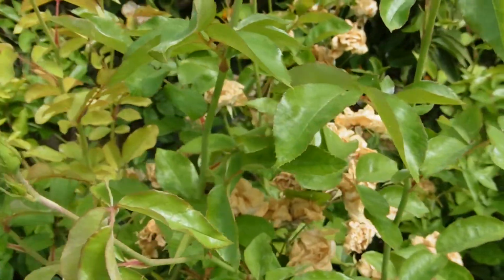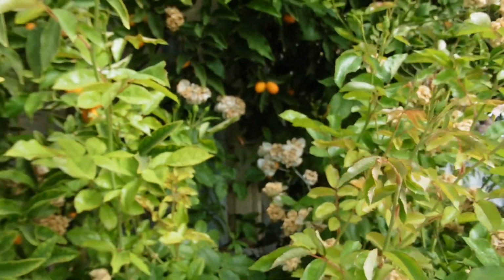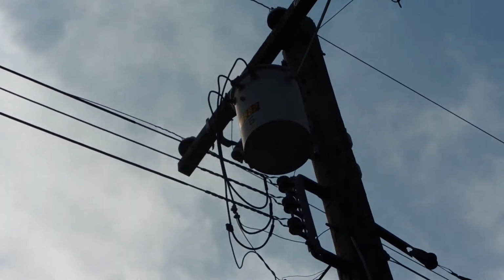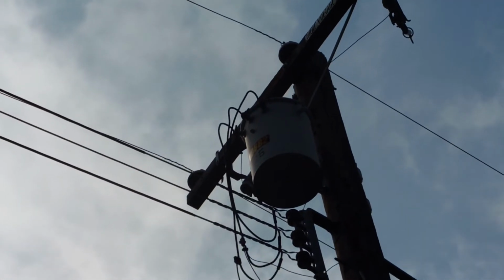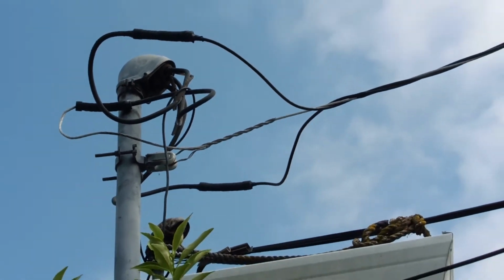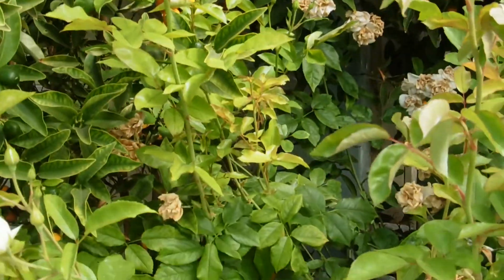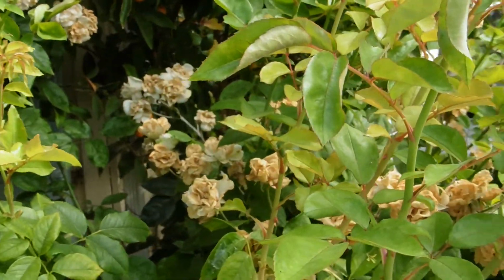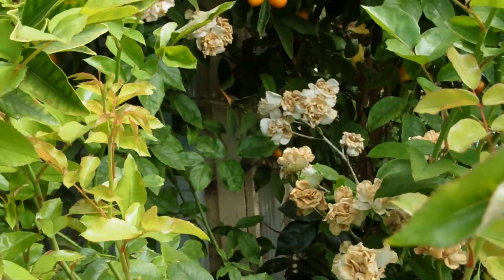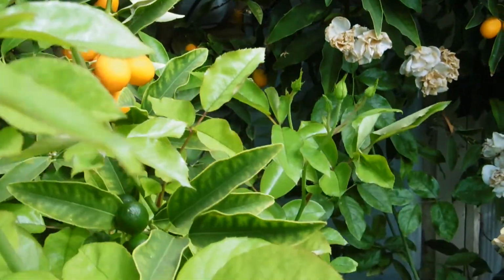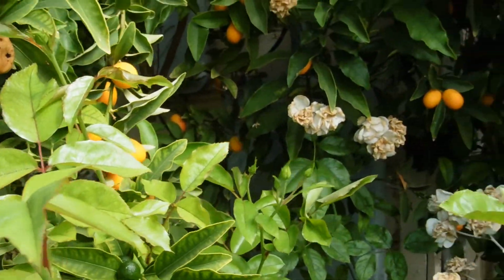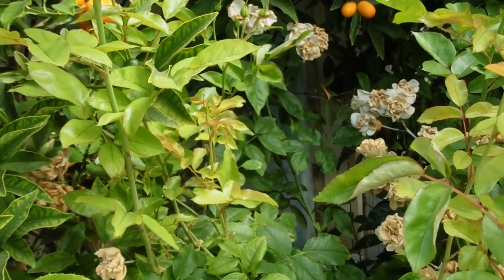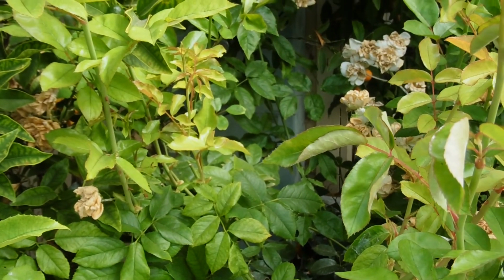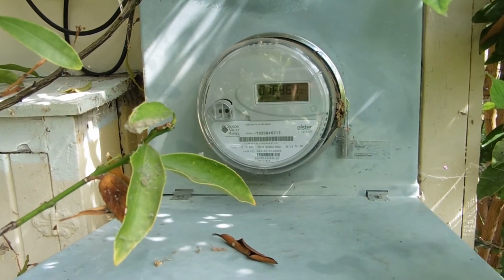And in my case, the electrical service is in a service panel that's behind this bush, which is why I'm out here. But let's start with something important. Up here is the transformer that serves my neighborhood, and the wire that serves the house comes right here. Both of those are a limit to how much electricity can be brought into this house. But the main limit is the service panel. And in my case, the service panel is buried way behind this kumquat tree and this rose bush. To get to that, let me get it out of the way, and I'll stop the recording for now and take care of that. Okay, so I've gotten things out of the way so we can take a look at this.